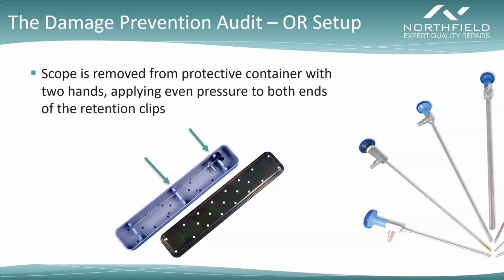Now, there's a couple of caveats that we have to talk about. First off, notice in the picture that this particular holder has the retention clips that apply pressure to the scope at the eyepiece and in the middle of the shaft. And the one that's down towards the distal tip is actually a little bit larger because it's designed to hold another eyepiece. So this is a very common design for a rigid endoscope container, because essentially what it does is it allows you to put the scope in either direction. And when that is the case, it's very important to notice that the retention clips that actually apply pressure to hold the scope in place, that's where you want to pick the scope up.